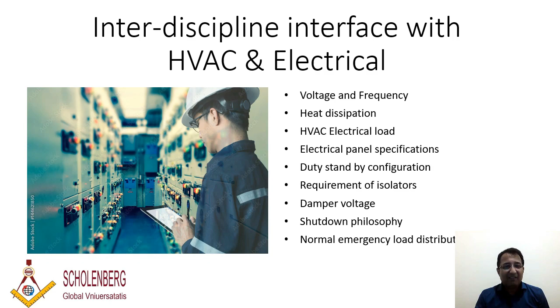So you reduce the load and put it on the diesel generator, which provides just enough air conditioning for 4 hours for the people gathered at that location. This requirement also needs to be informed to electrical - that these people will stay here, and other loads should not be taken off - so he accounts for that load when designing the emergency diesel generator. So this input also we need to give to electrical. There's a lot of give and take between electrical and us, so we need to always keep this in mind.